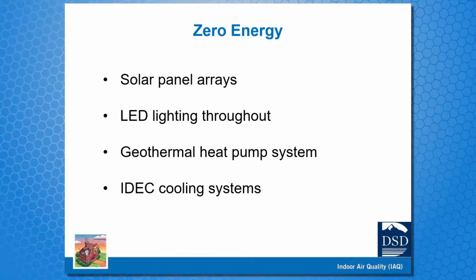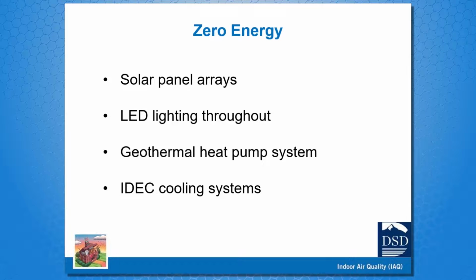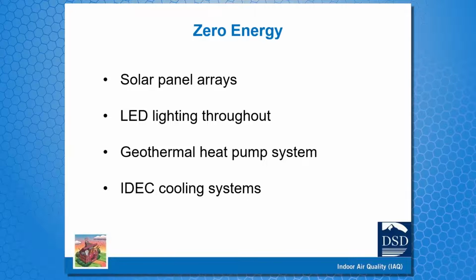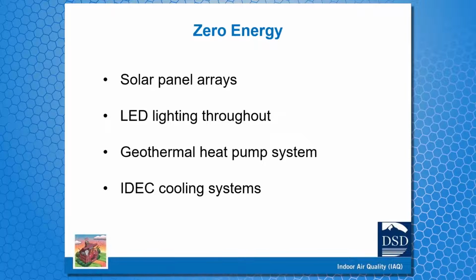We do a lot of ground source heat exchange systems, using heat pumps in the building. We use thermal air displacement, which helps us keep our fan speeds low and reduces how much we have to cool. Our climate is very conducive to evaporative or IDEC cooling, so we use that a lot here - basically a gigantic swamp cooler in the building.